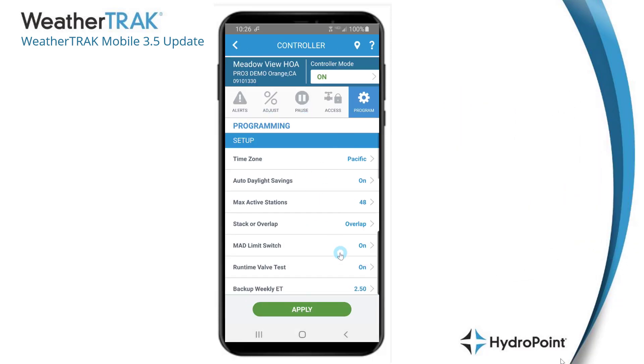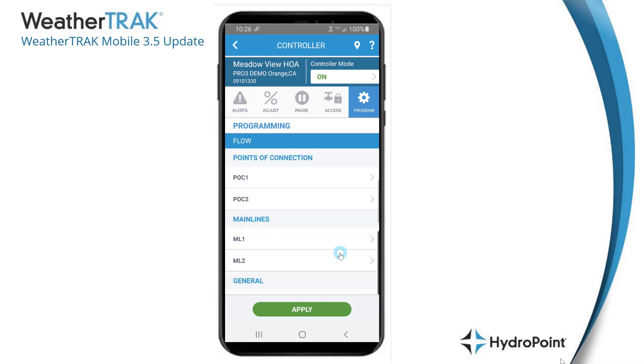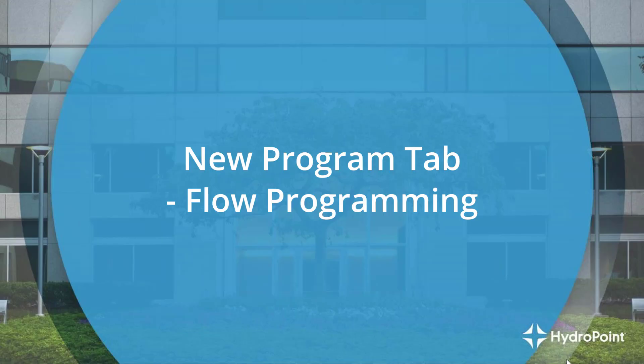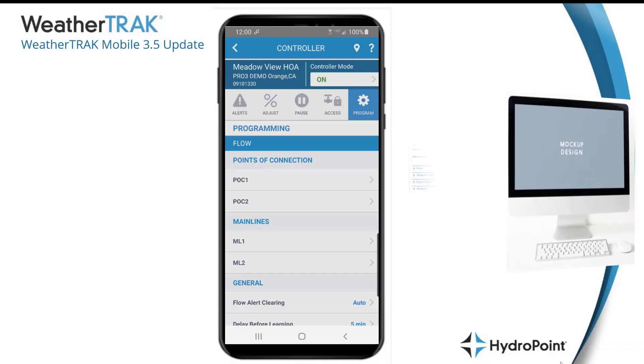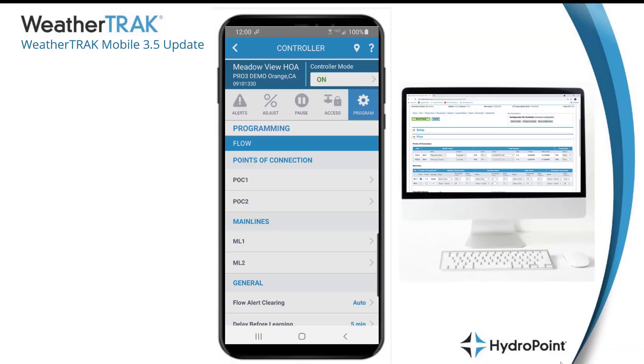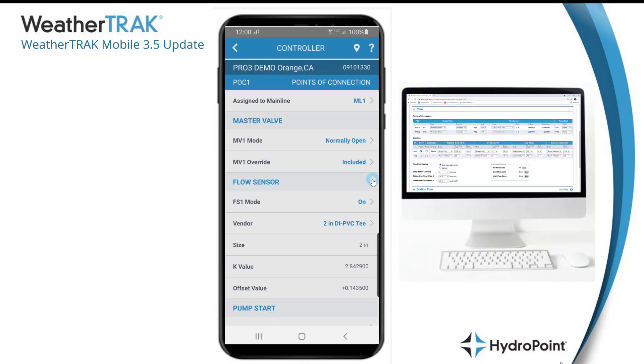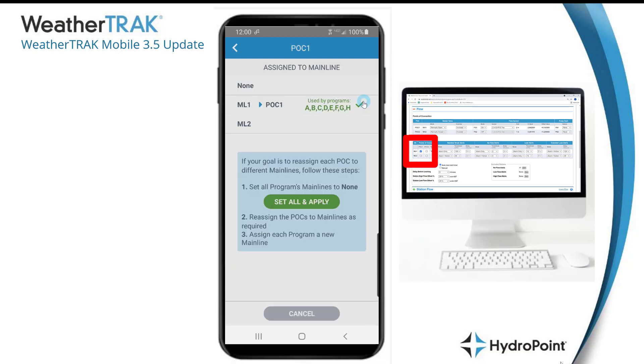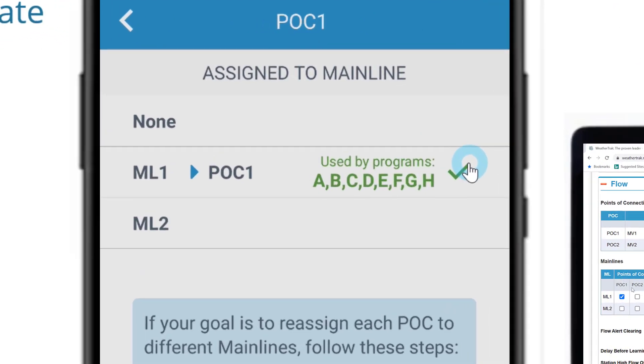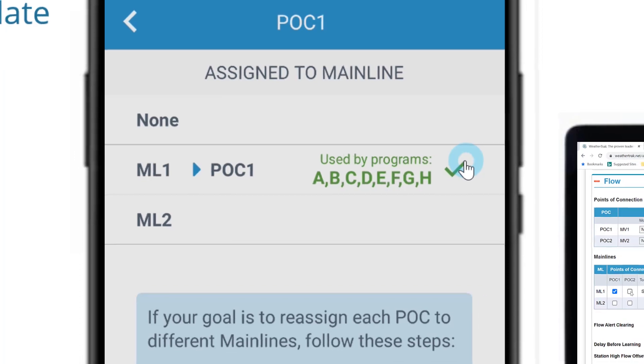After correctly filling out all the items on the setup menu, we can scroll down to program all the details of our flow components. The first thing to do on the flow menu is manage our points of connection. Select POC 1, click forward, and you'll see all the details of the first point of connection. To get it properly programmed, address the "assigned to mainline" question. Here we can see that POC 1 has been assigned to mainline 1 and all programs on this controller — A through H — have been assigned to that mainline.